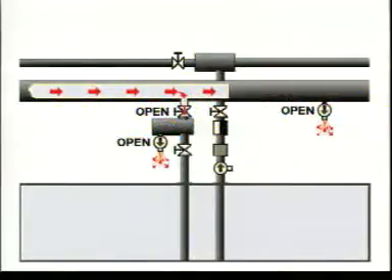The next step is the most laborious one. All coils must be checked for leaks and traces of oil. Water must be circulated through every coil and passed to deck via the drain cocks. The entire length of the coils must be flushed through. This will take some time.